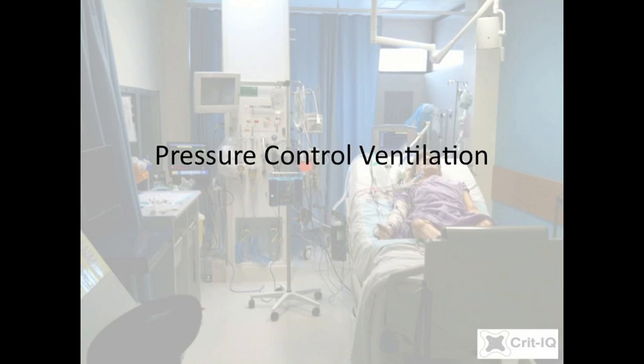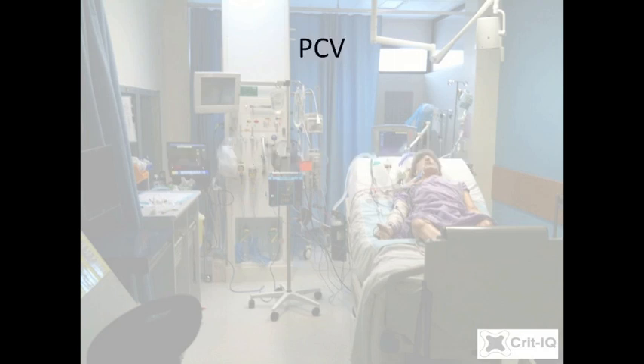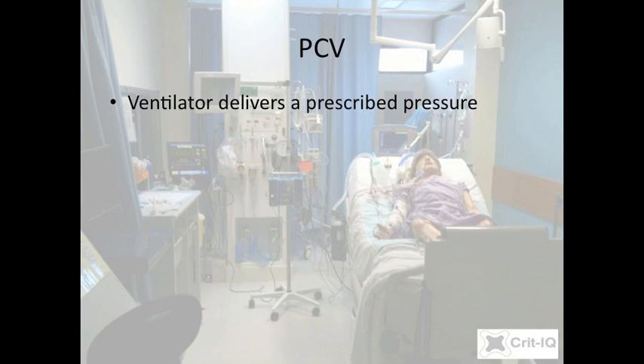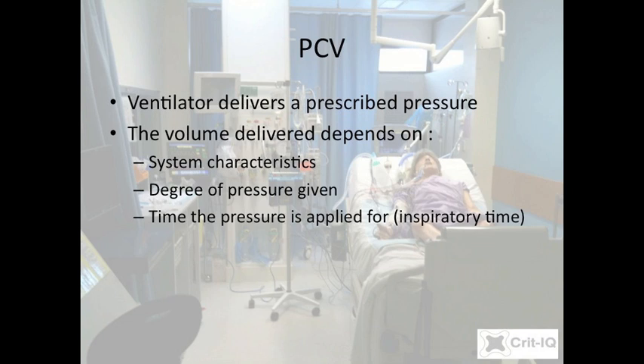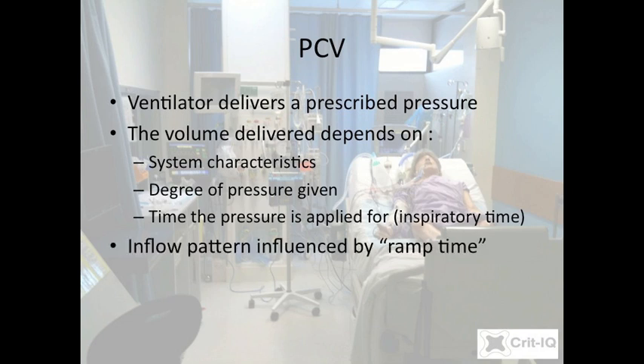Pressure control ventilation is very similar to CMV, differing in that instead of prescribing a specific volume, the ventilator delivers a specific pressure. The volume delivered is determined by the characteristics of the system, the degree of pressure set, and the time that the pressure is applied for. Similar to CMV, the pressure is applied for a specific inspiratory time, analogous to the IE ratio. The profile of inflow can be manipulated by adjusting the ramp time — the rate at which the ventilator achieves the set pressure — though in practice this is rarely adjusted.